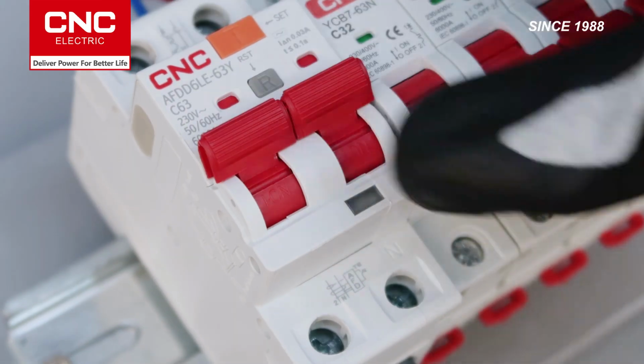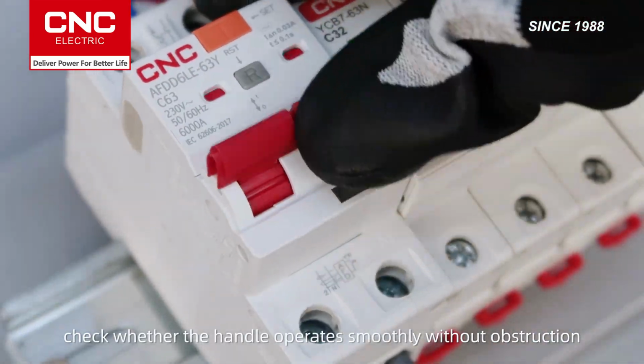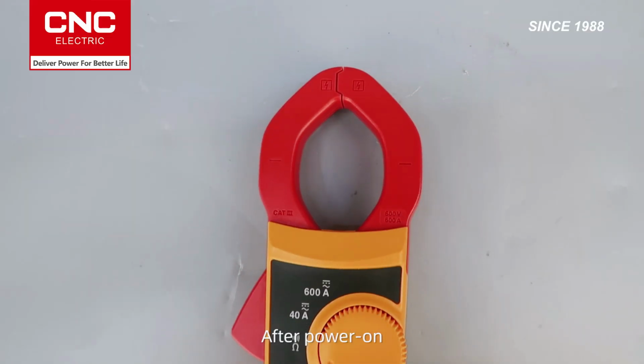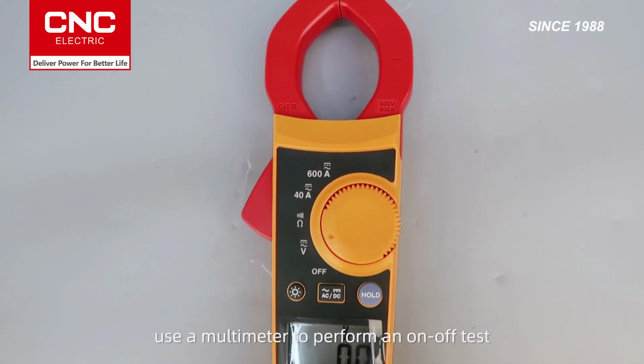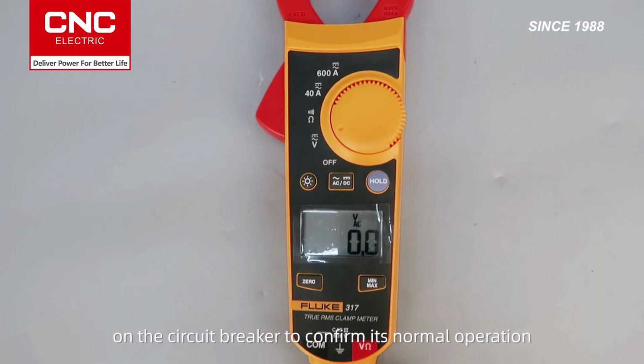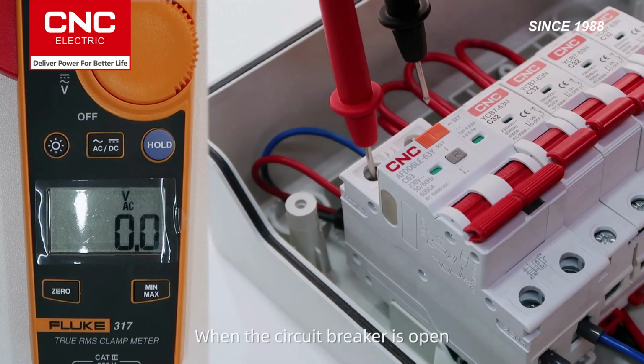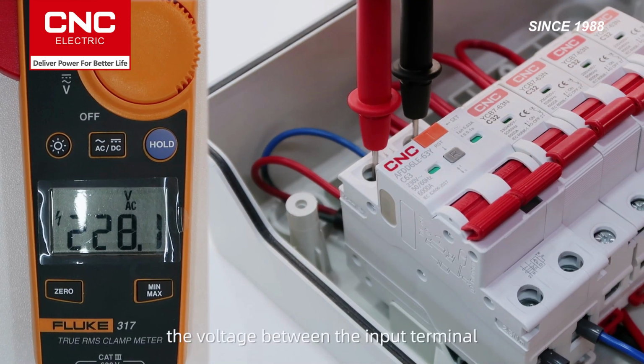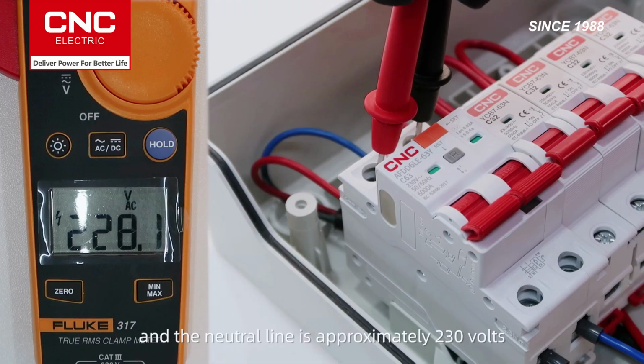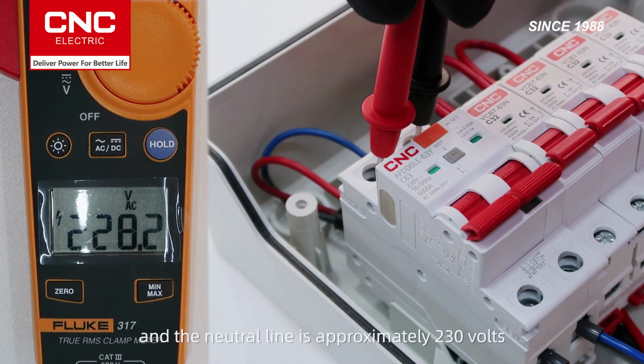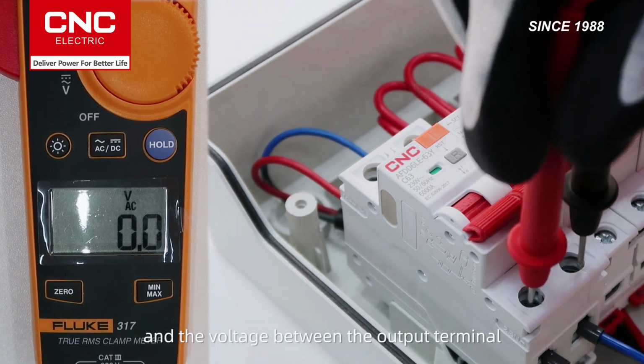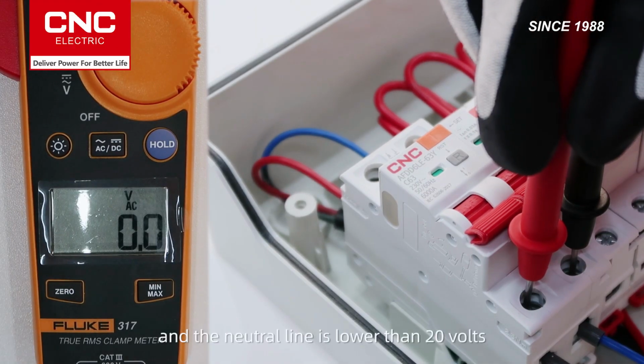Before power on, check whether the handle operates smoothly without obstruction. After power on, use a multimeter to perform an on-off test on the circuit breaker to confirm its normal operation. When the circuit breaker is open, the voltage between the input terminal and the neutral line is approximately 230 volts, and the voltage between the output terminal and the neutral line is lower than 20 volts.